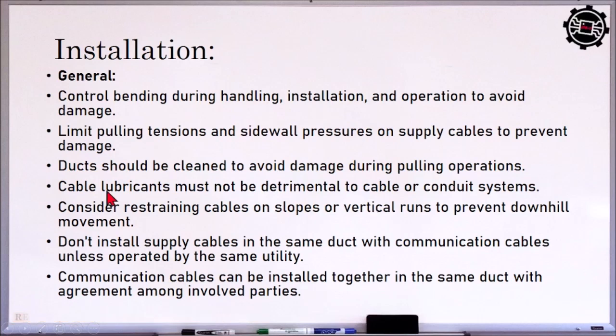Cable lubricants must not be detrimental to cable or conduit systems. So if we are going to use lubricant to facilitate the pulling of our cable, dapat hindi siya detrimental, meaning hindi siya nagre-react doon sa insulation ng ating cable. Consider restraining cables on slopes or vertical runs to prevent downhill movement. So if in case our cable is nadaan siya sa pa-slope, pa-slant or pa-vertical, pataas, dapat meron tayong way to support. Pwede natin gamitan ng cable tie or strap para yung ating cable will not be going pababa, which will cause na mag-clog yung ating ducting or yung dadaanan ng ating cable.